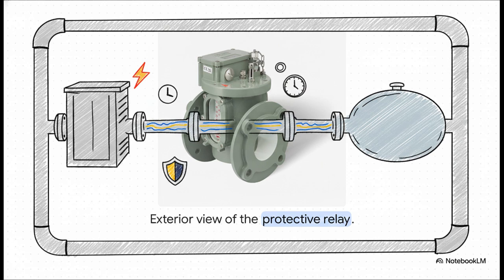So what you're looking at here is the exterior housing of the relay itself. It's physically bolted right into the pipeway between a transformer's main tank and its oil conservator, which is basically just a giant expansion tank for the fluid. It's literally sitting right there in the flow of the insulating fluid, acting as this relentless, silent sentry that monitors the health of the transformer 24/7.